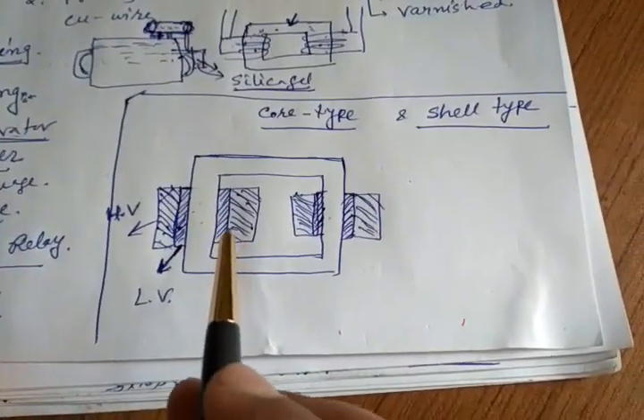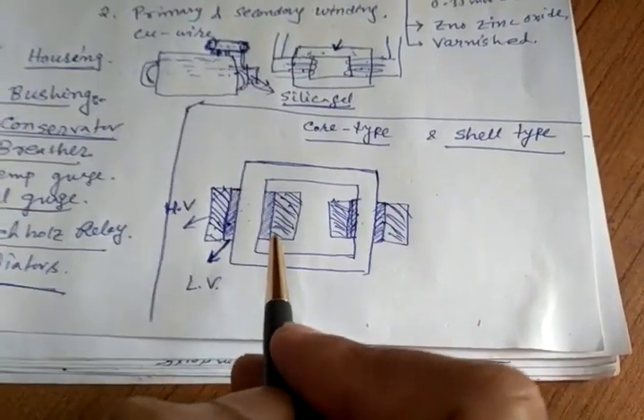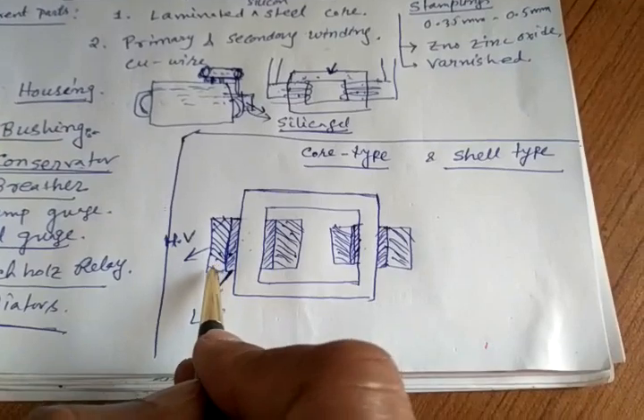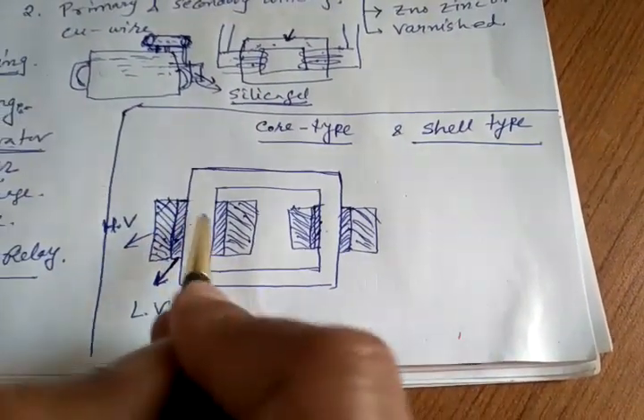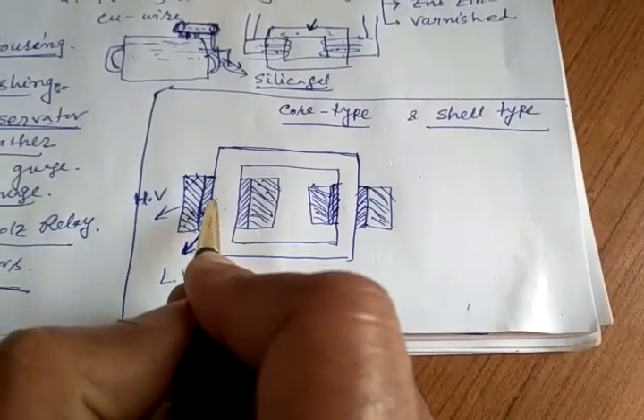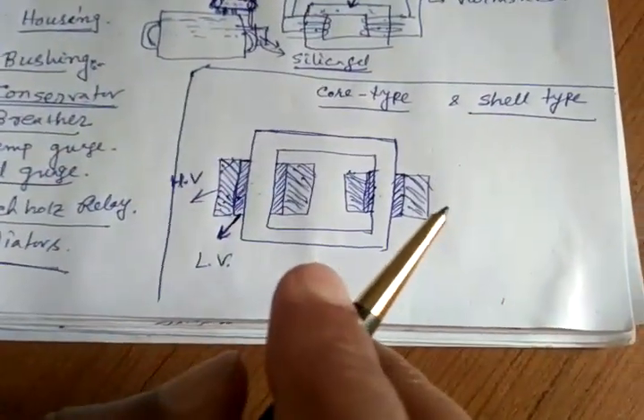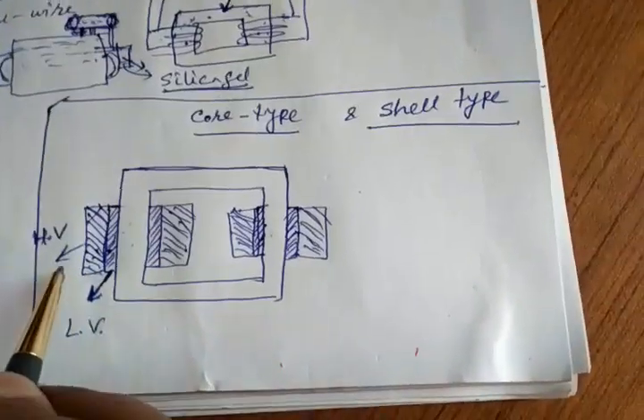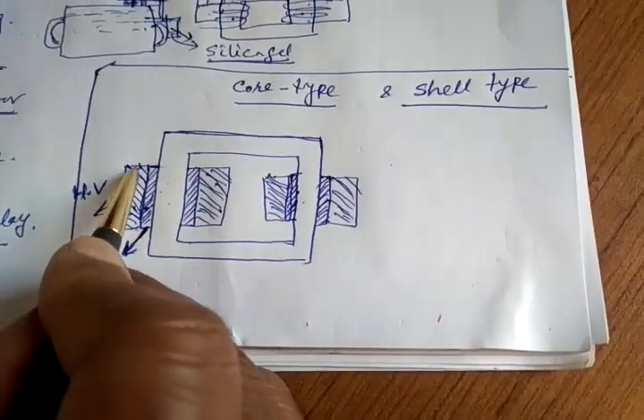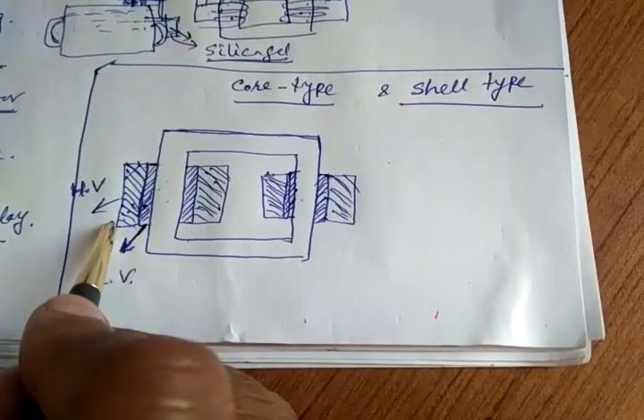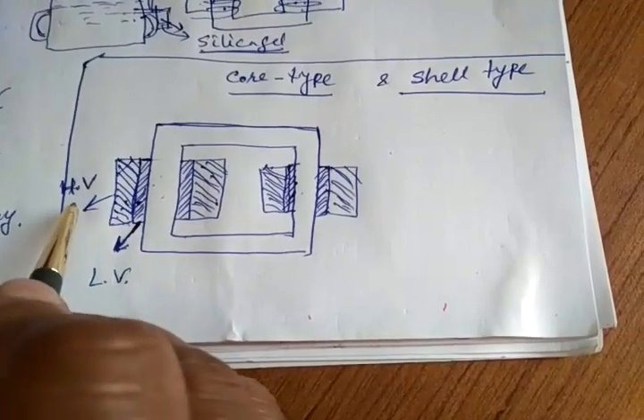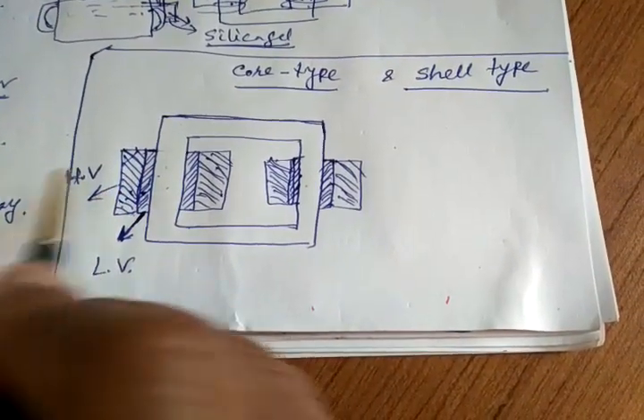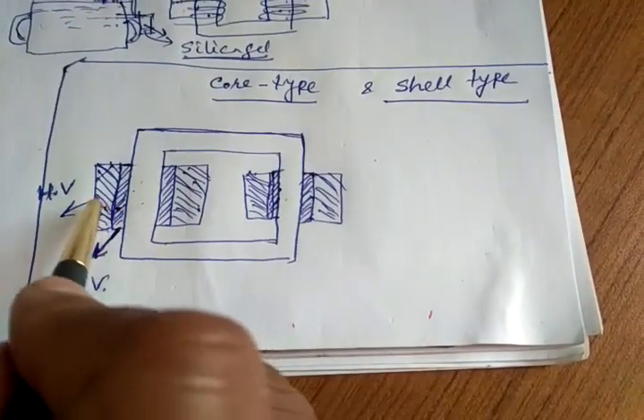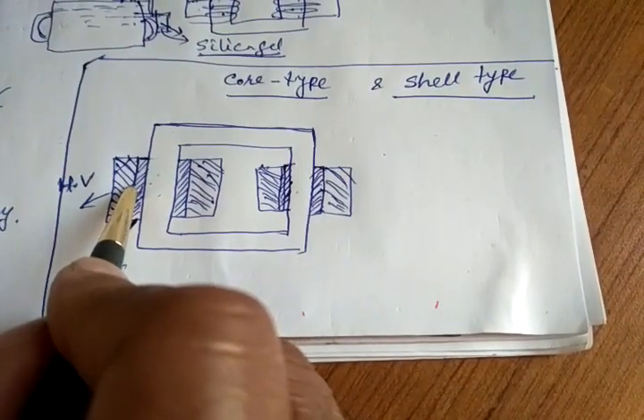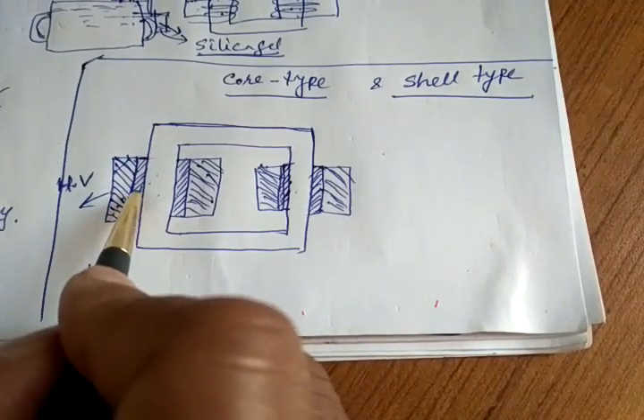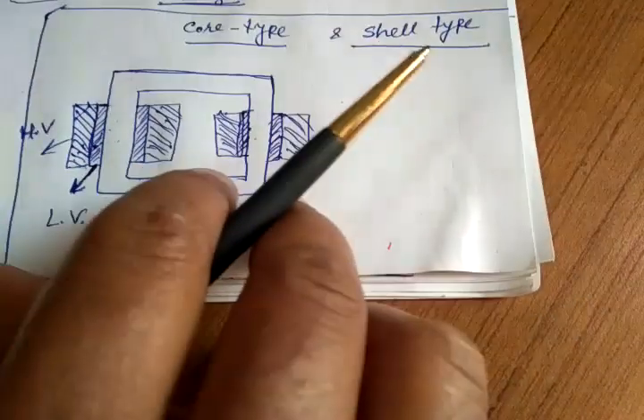Another advantage is from the perspective of maintenance. If some fault occurs, generally most of the faults occur in the high voltage winding, because the low voltage winding doesn't have many problems or faults. Most of the faults occur in the high voltage winding, and so the repairing is very easy, because only the last final insulation has to be removed and the repair done, then it is put back again. But if it were the other way around, with the high voltage winding below, then we would have to take away the high cost high voltage insulation to repair. So in that way also this type of construction helps.